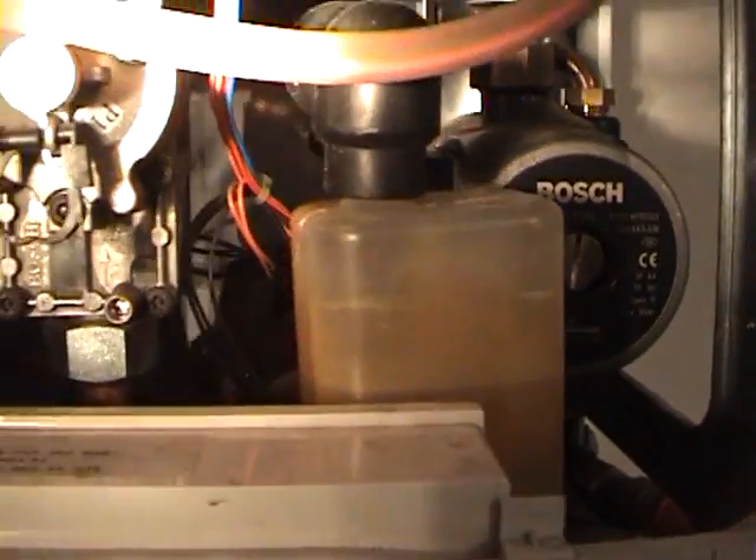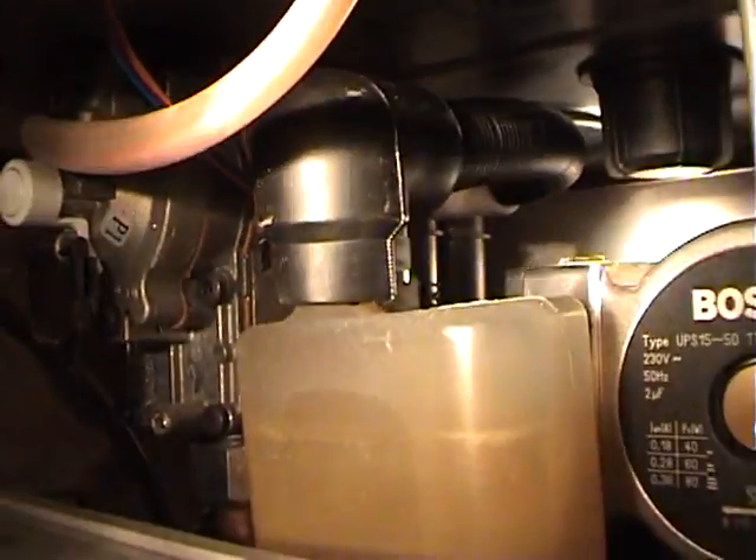So it's not the simplest — it's a very common fault, but it's got two causes. So that's what you have to do: take that off and clear it out, make sure you check past it. There's a pipe there — I'm shining my light on it — that rubber pipe there needs to make sure it's clear.